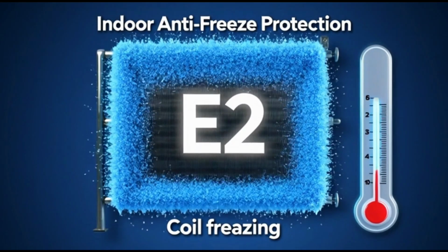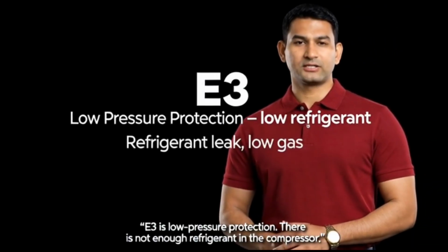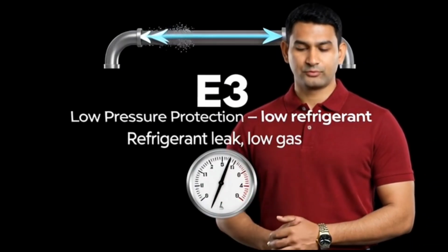E2 is antifreeze protection. The AC shuts down if the indoor coil gets too cold. E3 is low pressure protection. There is not enough refrigerant in the compressor. Refrigerant gauge showing low pressure.